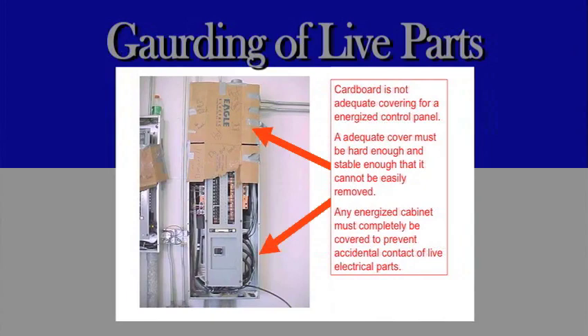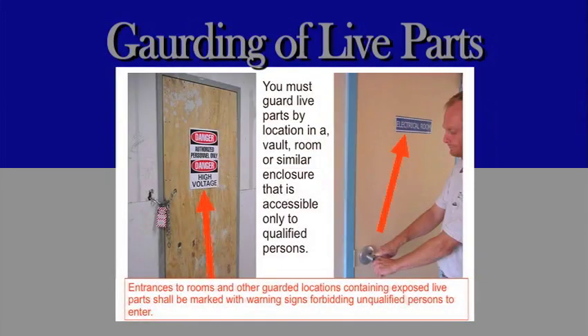Guarding of live parts. Cardboard is not adequate covering for an energized control panel. An adequate cover must be hard enough and stable enough that it cannot easily be removed. Any energized cabinet must be completely covered to prevent accidental contact with live electrical parts. You must guard live parts by location in a vault, room, or similar enclosure that is accessible only to qualified persons. Entrances to rooms and other guarded locations containing exposed live parts shall be marked with warning signs forbidding unqualified persons to enter.